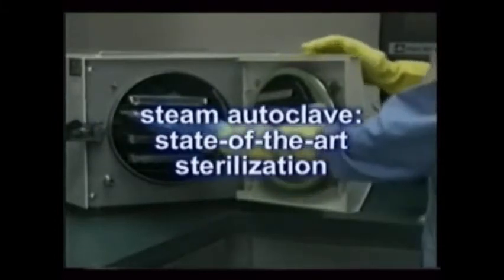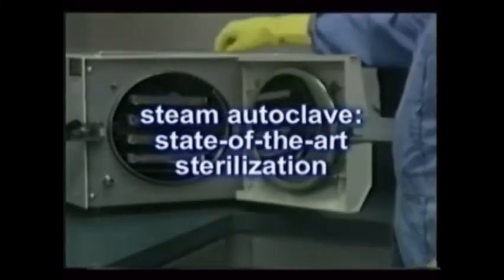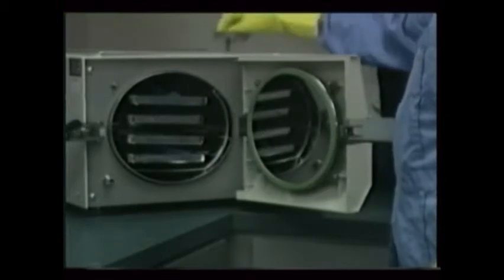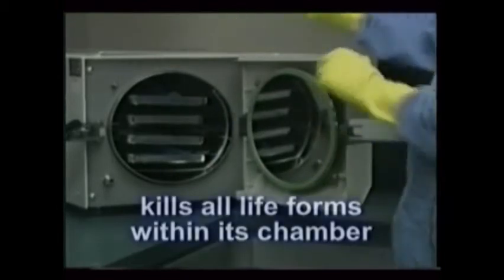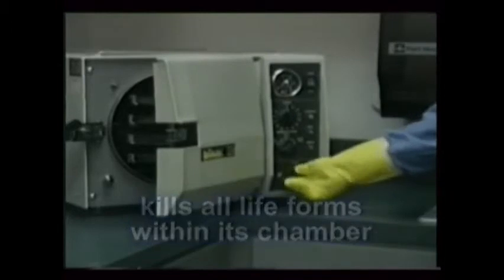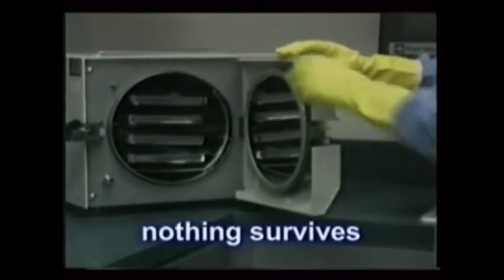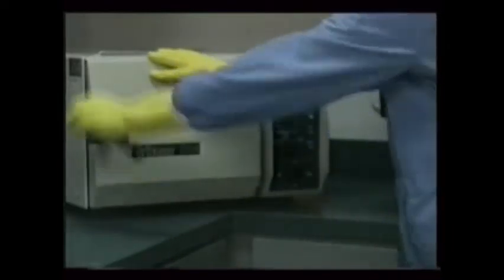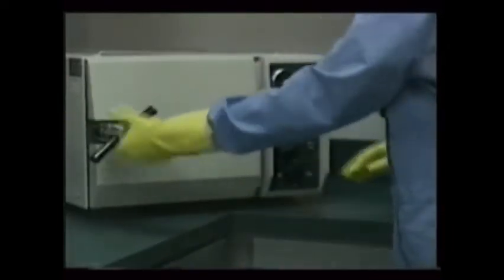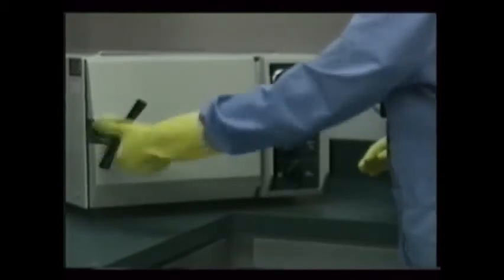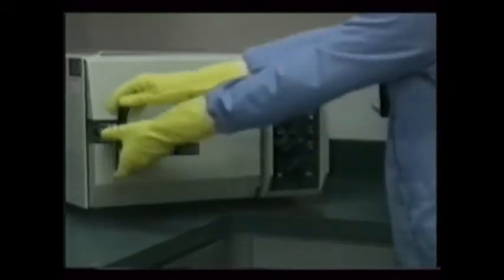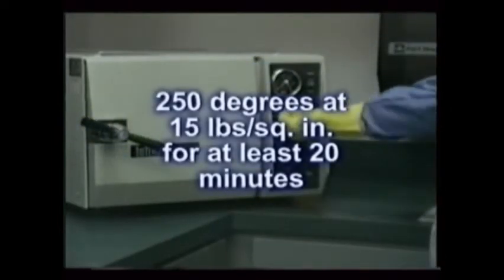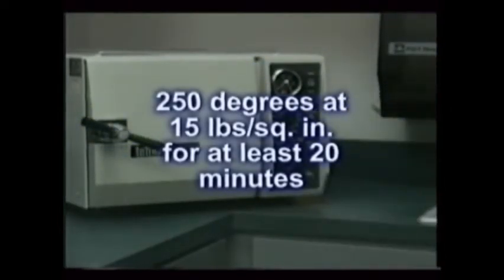The state-of-the-art method of sterilization in the dental office, though, is the steam autoclave. It uses extremely high pressure, high heat, and steam to kill all forms of life within its chamber. Absolutely nothing survives. Some machines automatically monitor the process using computer chips, and others require your intervention. It's important to always remember that sterility is only guaranteed if the instruments are exposed to the 250 degree and 15 pound per square inch conditions for at least 20 minutes, and even longer if the load is large.